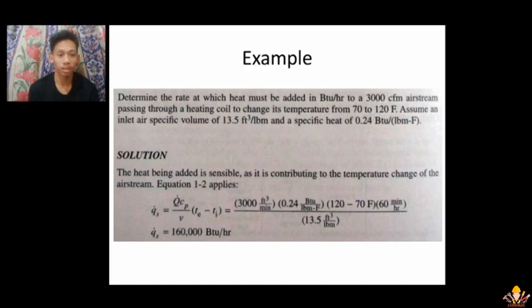Equation 1-2 applies. Our formula is the rate of sensible heat transfer equals the volume flow rate times the constant pressure specific heat over the specific volume times the temperature at the exit minus the temperature at the inlet. Substituting the given values, we have 3000 cubic feet per minute times 0.24 BTU per pound mass Fahrenheit, that is our constant pressure specific heat. For the temperature exit minus temperature inlet, we have 120 minus 70 Fahrenheit, and 60 minutes per hour. The specific volume is 13.5 cubic feet per pound mass. So our rate of sensible heat transfer is 160,000 BTU per hour.